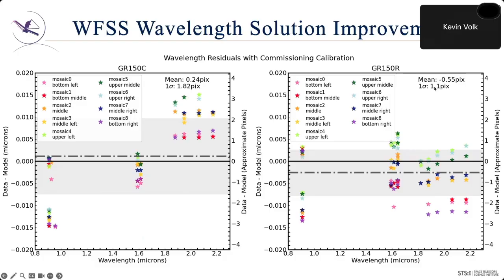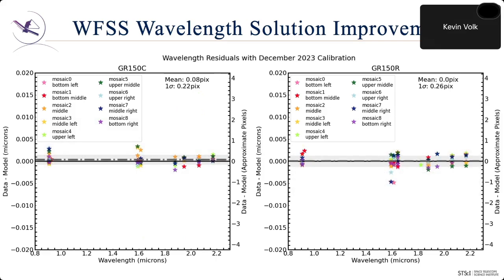For the other one, it's slightly better sigma. It's only 1.1 pixels, but the mean is actually more offset. So that's what we had in our initial crude calibration. And this is what we have now from December 2023 calibration. And you see the points are all tightly grouped by comparison, and now our mean is close to 0 pixels, and the 1 sigma is about 1/4 of a pixel, depending on which of the two GRISMs. So this is much better than it was before, and hence the wavelength calibration is much improved.